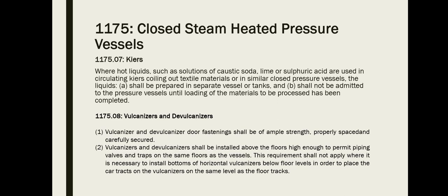Next is Rule 1175.08, vulcanizers and devulcanizers. One, door fastening shall be of ample strength, properly spaced and carefully secured. So dapat naka-properly spaced o carefully secured ang vulcanizer o devulcanizer. Then two, vulcanizers and devulcanizers shall be installed above the floor high enough to permit piping valves and traps on the same floor as the vessels. So dapat ang vulcanizer o devulcanizer is naka-installed above floor nga enough para maka-permit sa piping valves and traps. Then this requirement shall not apply where it is necessary to install bottoms of horizontal vulcanizers below floor levels in order to place the car tracks on the vulcanizers on the same level as the floor tracks.